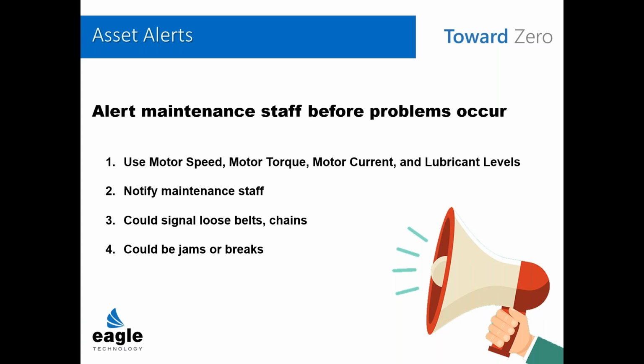The other thing we can do with that data is alert maintenance staff that something's going to happen before it happens. This takes a bit more knowledge of the system itself in order to set those limits. Typically, what we recommend is giving the maintenance staff a tool where they can change those set points themselves and adjust the thresholds that alert them. We're all bombarded with too many emails and too much communication these days, so it's important not to overdo this. The idea is to look at critical assets and ask why it went out of tolerance, or why it broke the last time, and what we can monitor to alert us that it's going to happen again.